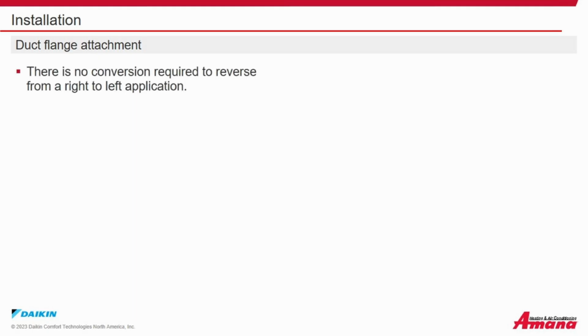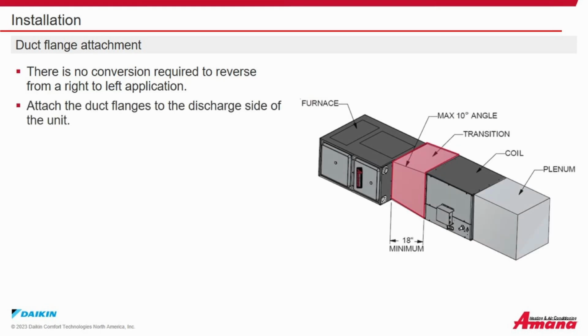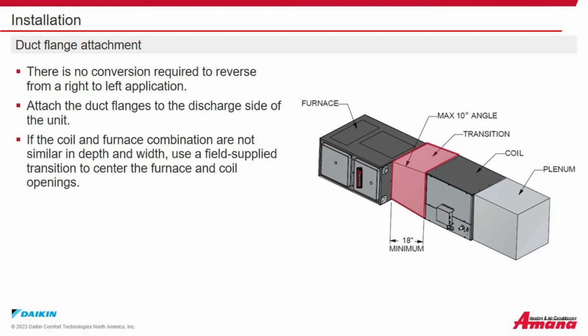Duct flange attachment. There is no conversion required to reverse from right to left application. Attach the duct flanges to the discharge side of the unit. If the coil and furnace combination are not similar in depth and width, use a field-supplied transition to center the furnace and coil openings.